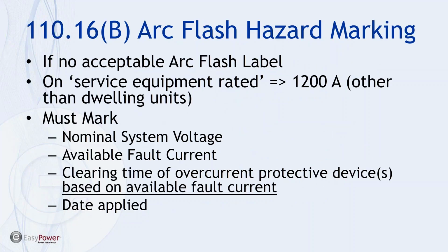The first is Article 110.16(B), and for starters, it suggests that an arc flash label may already be in place. So its criteria is if an acceptable arc flash label is not in place, then on service equipment rated for 1200 amps or greater, other than dwelling units, there must be a label that indicates nominal system voltage, available fault current, clearing time of overcurrent protective devices based on available fault current, and the date applied.